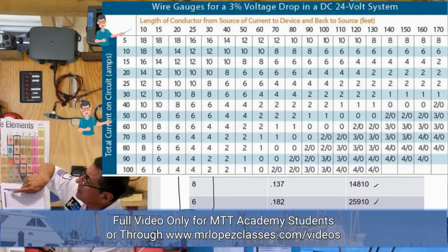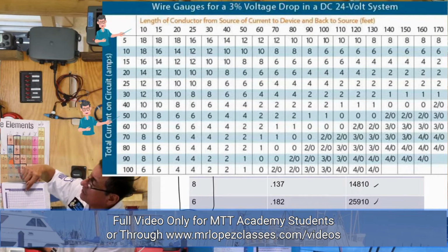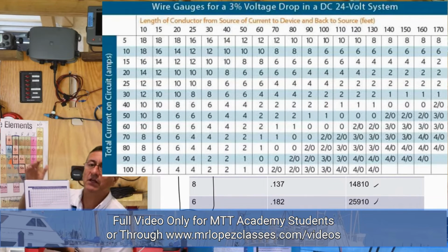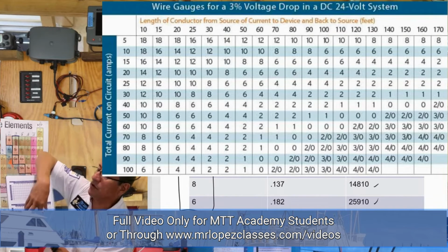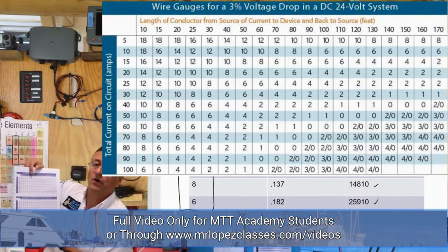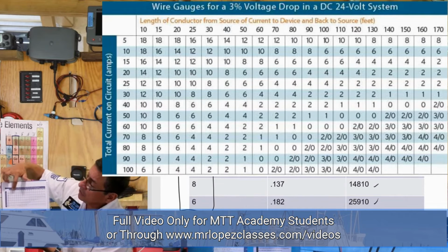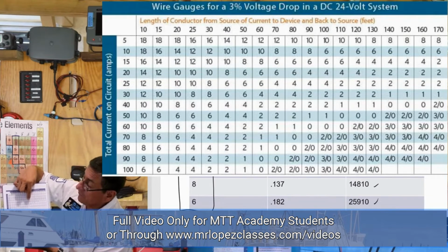On the left, in the column, you have the amps: 5 amps, 10, 15, 20, 35, 40, 60, 80, 100. I have the total length and I have the amps, and this is the gauge of the wire. It's too simple. This table, exactly the same table that you have on the screen right now, is for 3% of voltage drop, 12 volts here and 24 at the bottom. And this one is for 10% of voltage drop, for 12 volts and 24. On top you find the distance in feet. In this column, you have the intensity in amps. According to the intensity and the distance, you find the gauge.